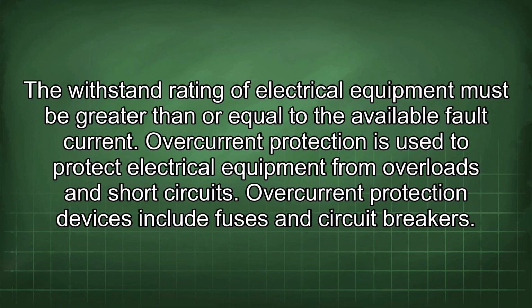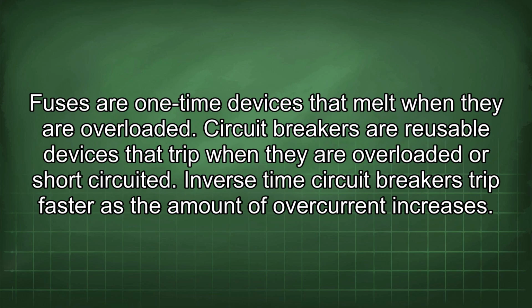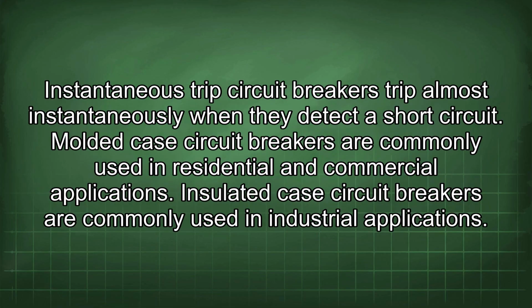Overcurrent protection is used to protect electrical equipment from overloads and short circuits. Overcurrent protection devices include fuses and circuit breakers. Fuses are one-time devices that melt when they are overloaded. Circuit breakers are reusable devices that trip when they are overloaded or short-circuited. Inverse time circuit breakers trip faster as the amount of overcurrent increases. Instantaneous trip circuit breakers trip almost instantaneously when they detect a short circuit.